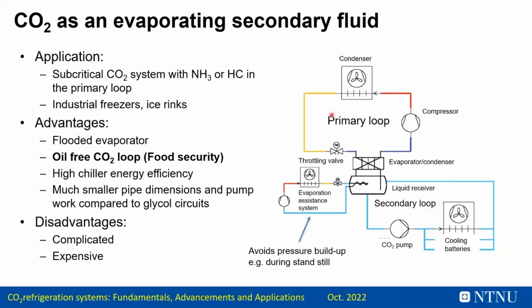And the important thing is, of course, the primary loop. It can be done with ammonia or hydrocarbons, and this is typically applied for industrial freezers, or even ice rinks are done like this. In case you have a non-continuous operation of your freezing plant, you need a cold finger to keep the CO2 at a certain pressure level to remove the heat leakage into the vessel to keep the charge inside. And this is typically done with a small R290 unit, just keeping the pressure at the level it should be, while the main systems are off.